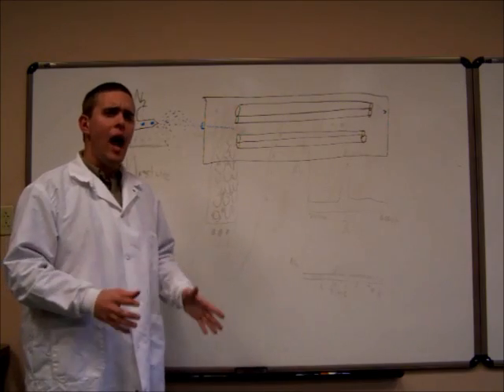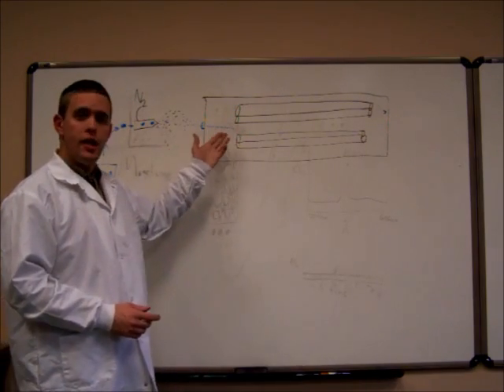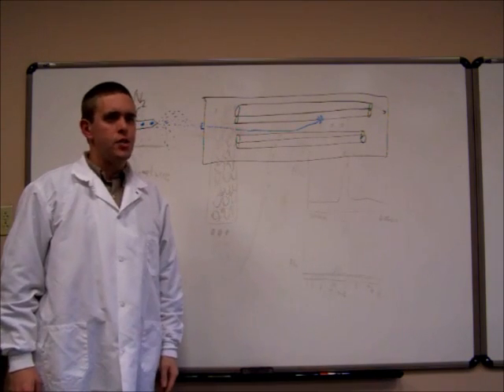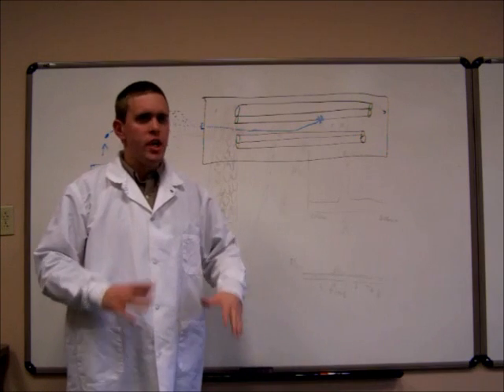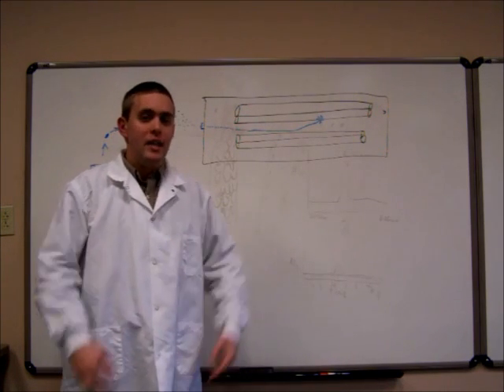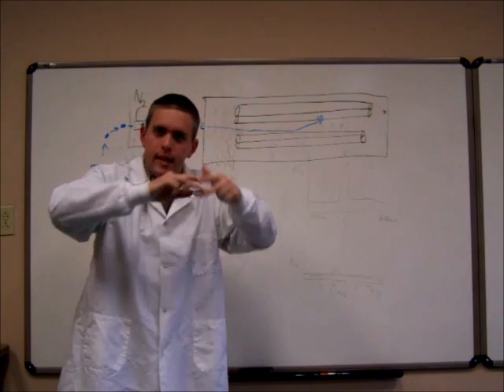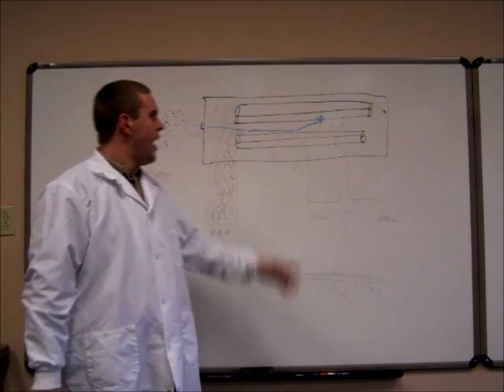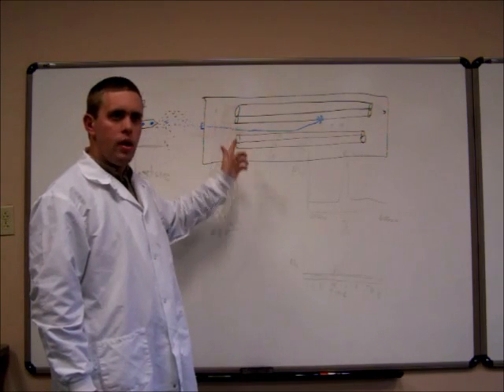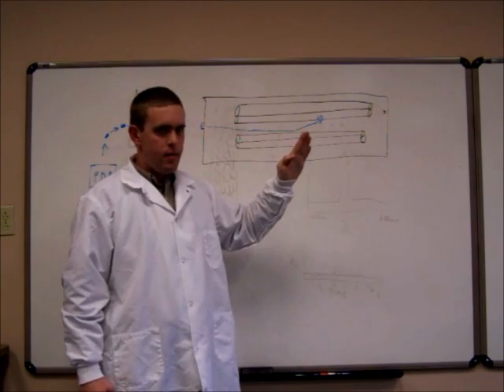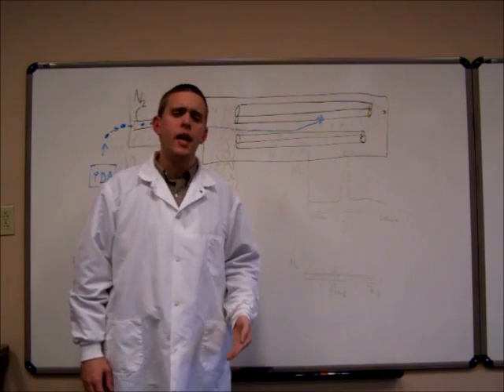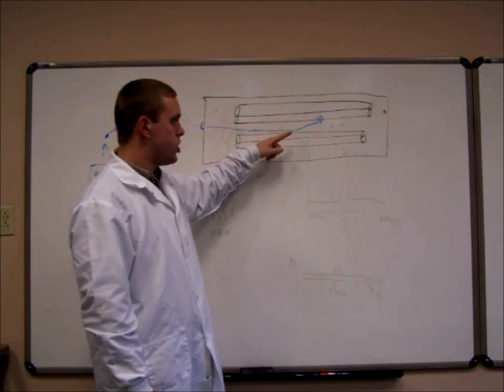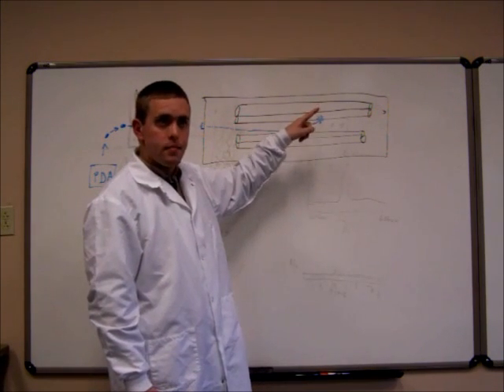Once our analyte has been ionized, it then enters into the quadrupole. The quadrupole is made up of four charged rods. These rods change their charge thousands of times a second, alternating between positive and negative charges. As the analyte enters the quadrupole, the charge deflects it. Most of the time, around 99% of the time, most of the analyte that enters the quadrupole, because of its charge, smacks right into it.